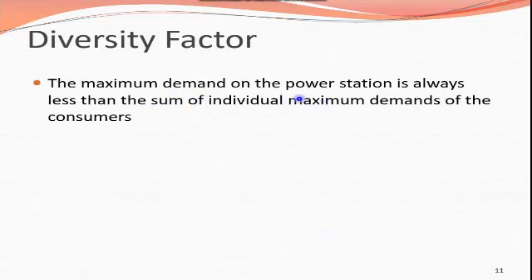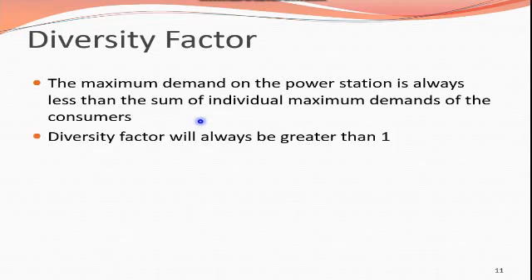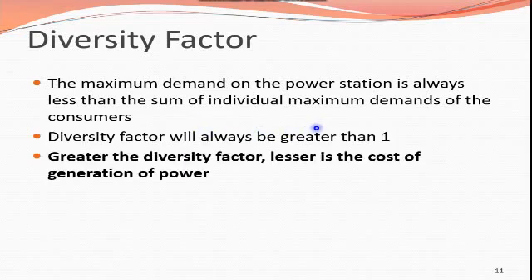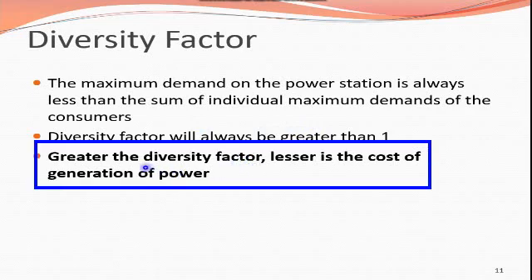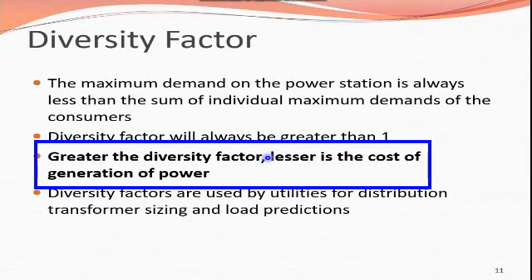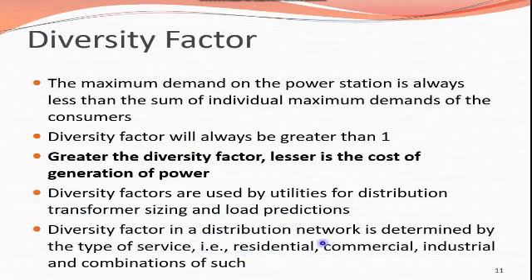The maximum demand on the power station is less than the sum of individual demands of consumers, meaning that some individual demands are always greater than the maximum demand on the power station. Therefore, the diversity factor will always be greater than one. The greater the diversity factor, the lesser the cost of generation of power. Diversity factors are used by utilities for distribution transformer sizing and load predictions, and are determined by the type of service: residential, commercial, or industrial.